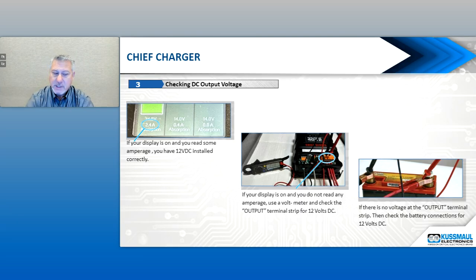If your display is on and you're reading amperage out of one of the battery outputs, you know you have a good connection to a battery. If your display is on and you're not reading any amperage, take your voltmeter and check — since it's a 3-bank charger, you don't have to use all 3 banks, you could have 1, 2, or 3 — make sure you're checking the right one, or all of them, to confirm you have the correct voltage on the output. Also double check that you have the right voltage coming in at the battery itself.